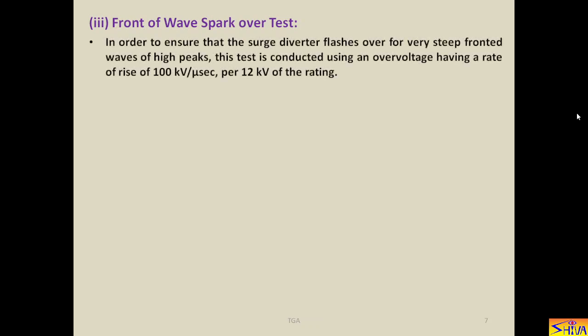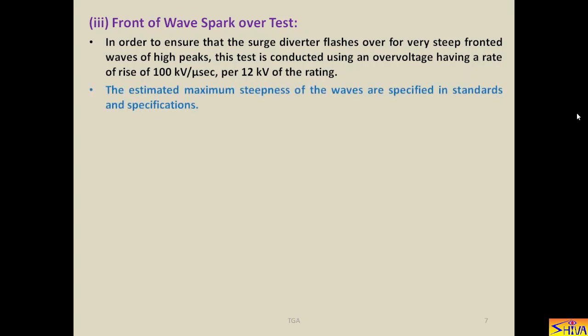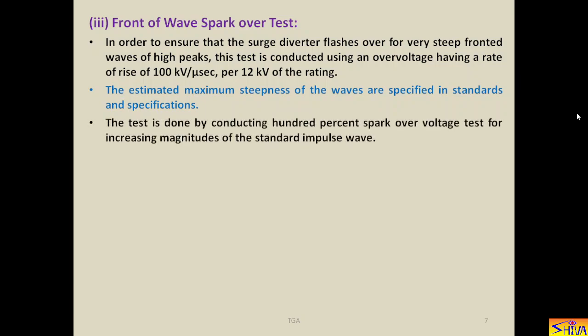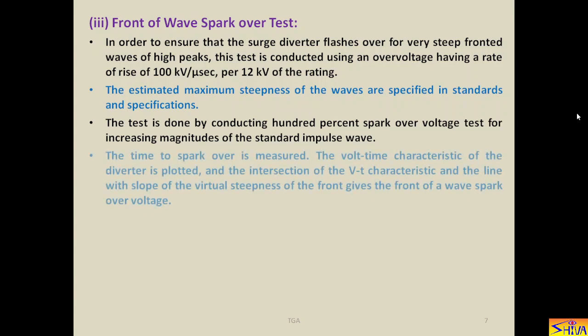In order to ensure that the surge diverter flashes over for very steep fronted waves of high peaks, this test is conducted using an overvoltage having a rate of rise of 100 kV per microsecond per 12 kV of the rating. The estimated maximum steepness of the waves are specified in standards and specifications. The test is done by conducting 100% spark over voltage test for increasing magnitudes of the standard impulse wave. The time to spark over is measured, the volt time characteristic of the diverter is plotted, and the intersection of the volt time characteristic and the line with slope of the virtual steepness of the front gives the front of wave spark over voltage.